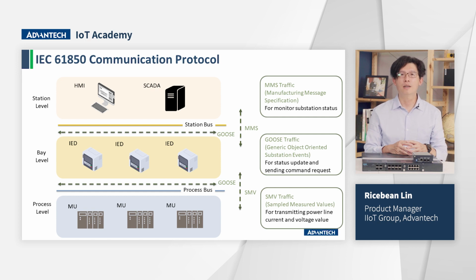Now we are going to talk about the communication protocol. The transmission protocol used to handle different types of data transfer is one of the main aspects of the IEC 61850 standard. The abstract data model defined in IEC 61850 can be mapped to a number of protocols, including MMS, GOOSE, and SMV. These protocols can run over TCP/IP networks to ensure a faster response time. MMS is used for the communication between the IED and the SCADA system for application communication and monitor data exchange. GOOSE is used to send a message regarding the status between the IEDs. The SMV protocol is related to the power line current and voltage measurement.